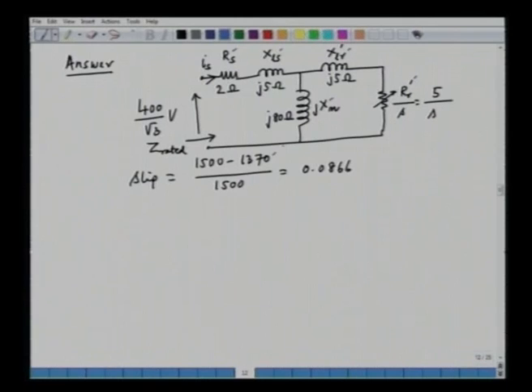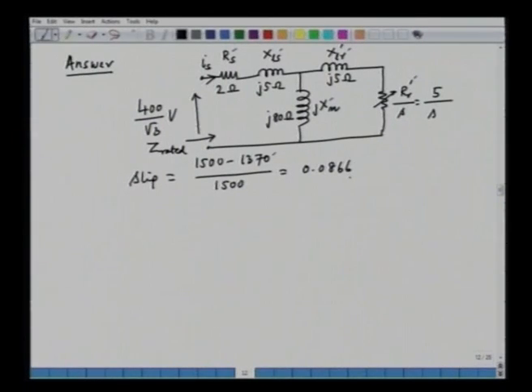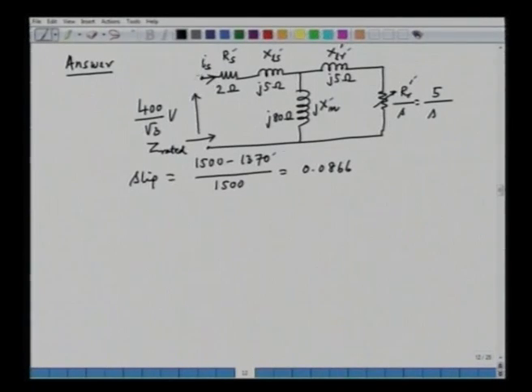The motor is operating at rated speed of 1370 rpm. We can find out the slip: synchronous speed is 1500 rpm, so slip s = (1500 - 1370) / 1500 = 0.0866. This is the rated slip of the machine. We have to find out the stator current I_s, and unless we find it, we cannot find ids and iqs. We know the slip, the motor parameters, and have the equivalent circuit.